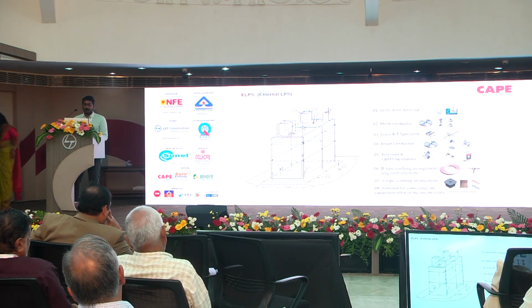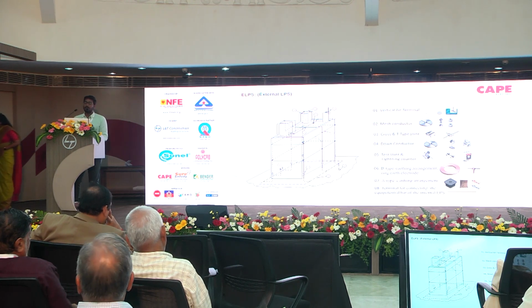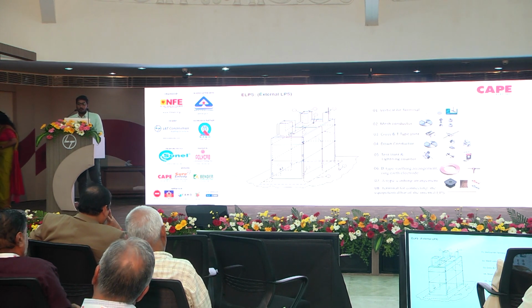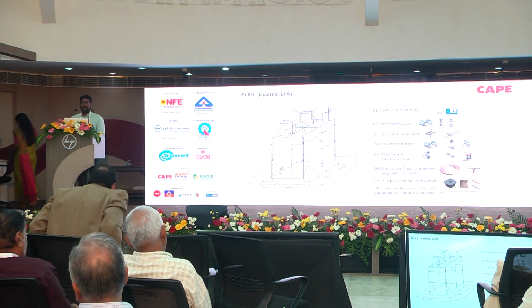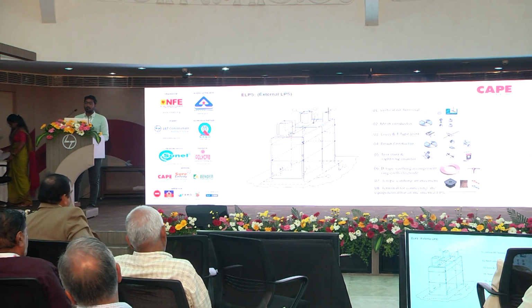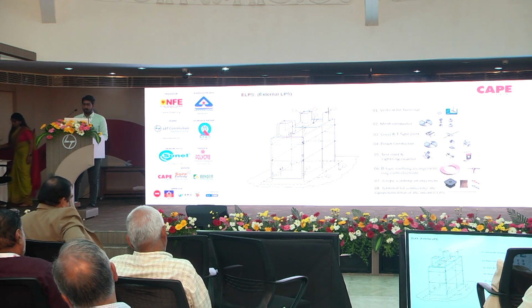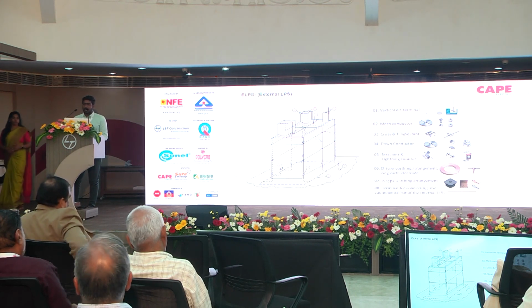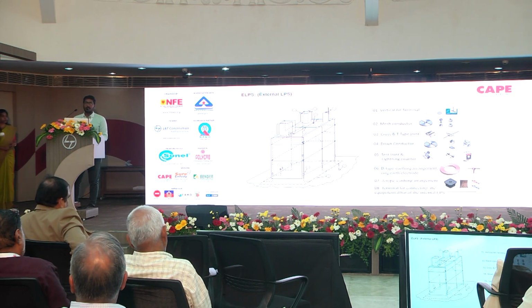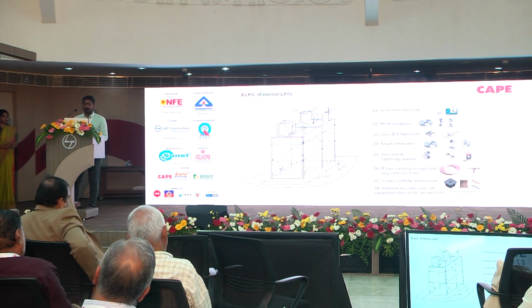Next, once the down connector is routed, the test link or test joint needs to be fixed at a height of 1.5 meters from the ground level. The test joint normally will be provided with an enclosure for future testing reference. And we'll fix a lightning counter over the test joint to know the lightning strikes which happen at the building. Then generally there are two recommendations for earthing, either type B or type A.